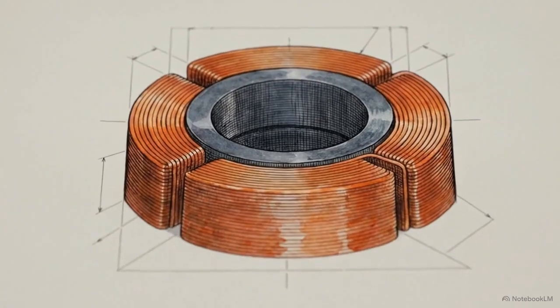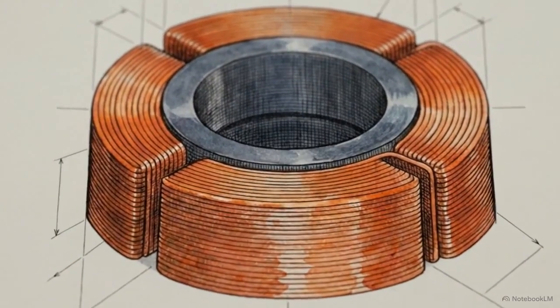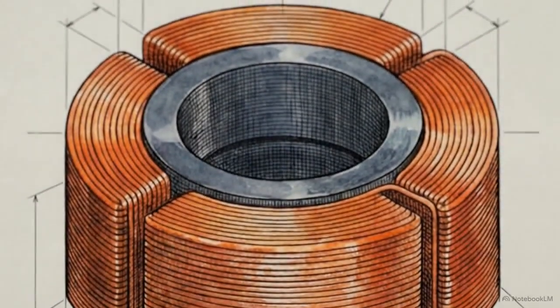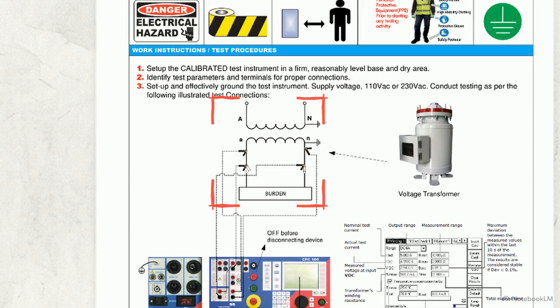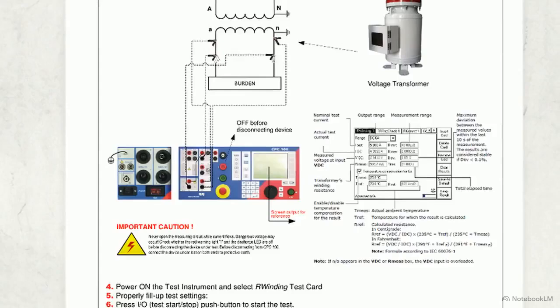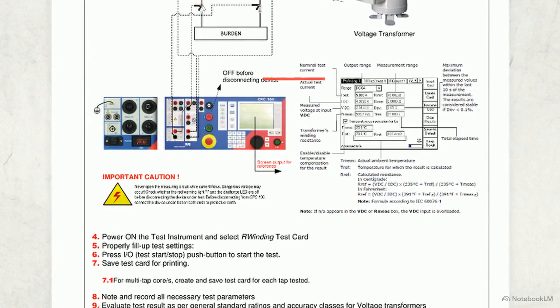With the external dielectric boundaries verified, the focus shifts inward to measure the exact ohmic health of the internal copper windings. Looking at the connection diagram, this requires a 4-wire Kelvin setup. Separating the current injection and voltage measurement leads at the terminals factors out test cable resistance. In the CPC-100 interface, the operator opens the winding resistance test card, entering target DC current and ambient temperature.